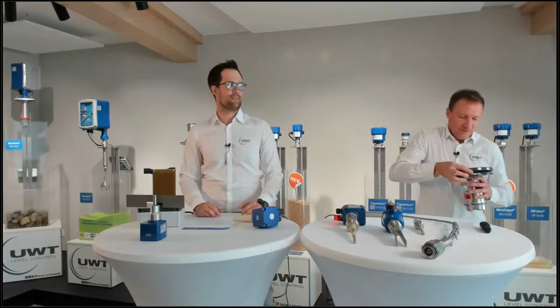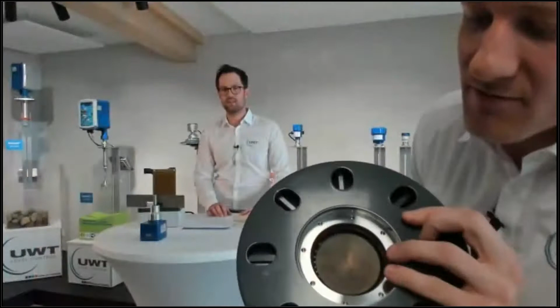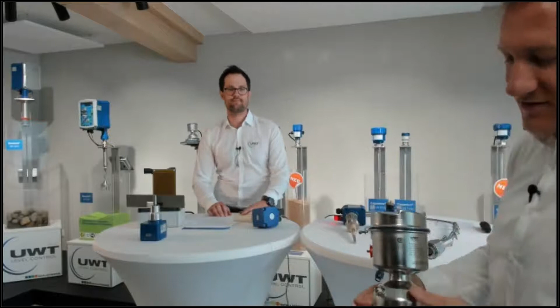If we have dusty material that covers the vane, maybe you can see in the camera these small holes where we can get rid of the dust with the air purge connection. The air purge connection is always integrated in the sensor, so you can also order it afterwards. So when you notice that you have some problems with the dust, you can just order it afterwards. Exactly. And then you have no problems with dusty buildup around the lens antenna. A little bit of dust is no problem, but if we have a real thickness of dust, then it can affect the measurement. But the dust has such a low DK value that it measures through the dust.